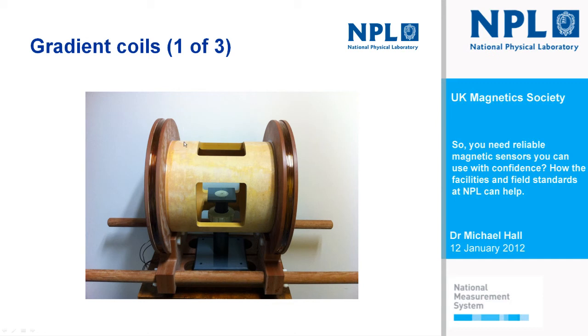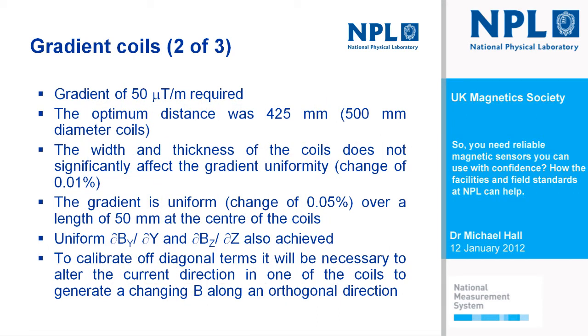A good gradient coil does not produce off-diagonal terms just because the matrix tensor shows that you can. This is what the profile looks like on the gradient coil that we have, and you can see that the variation over plus or minus 10 millimeters in the center is of the order of less than 0.01%. So that's very, very good.